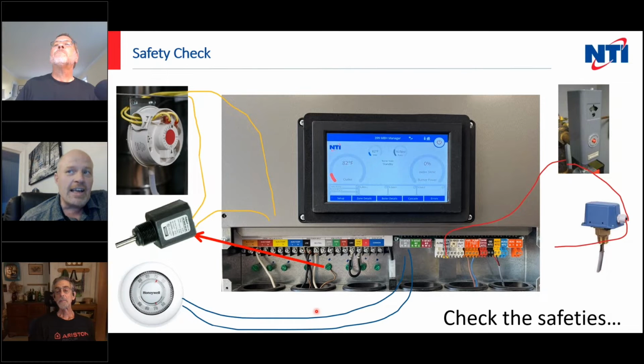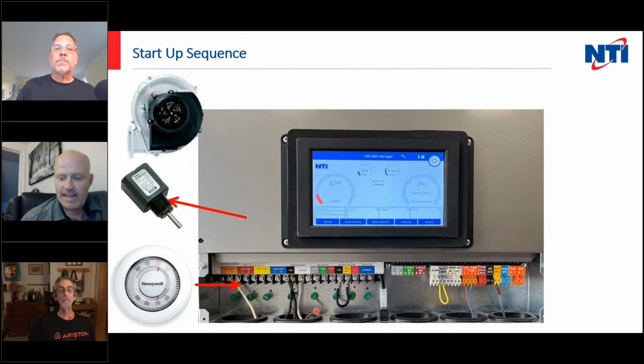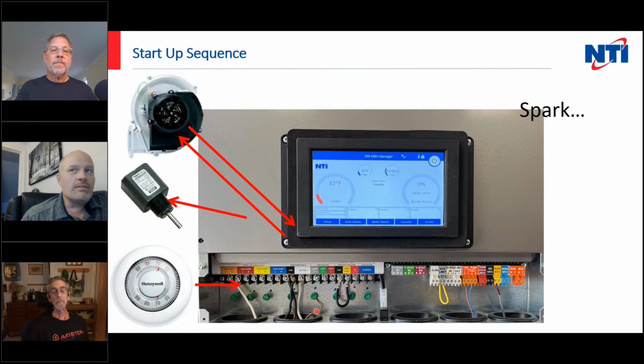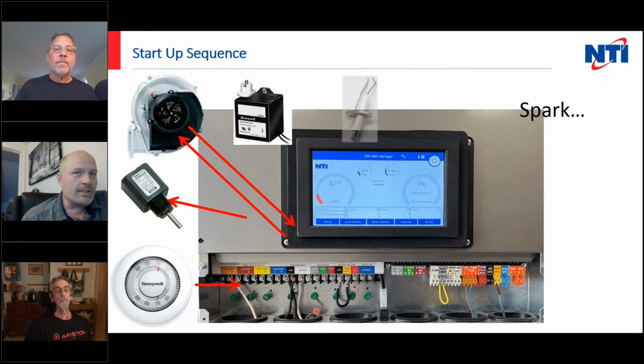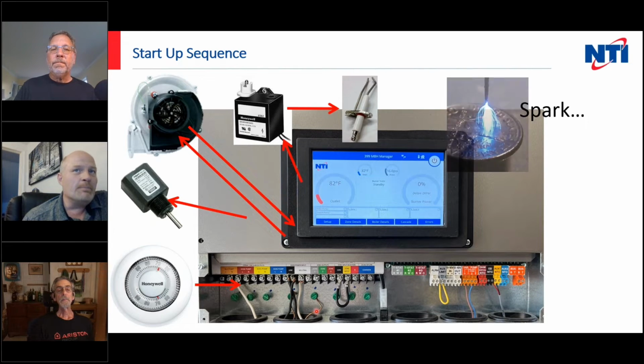We're then going to check any external safeties that might be wired on the auxiliary limit circuit. And once this is all verified and the inlet, outlet and stack temperatures are all within range, the boiler is then safe to proceed to the next step. So the next step is we're going to continuously monitor both the thermostat and the internal safeties. Then we send a signal to the blower, and the blower sends a signal back to us. If we don't get that signal, we don't light.